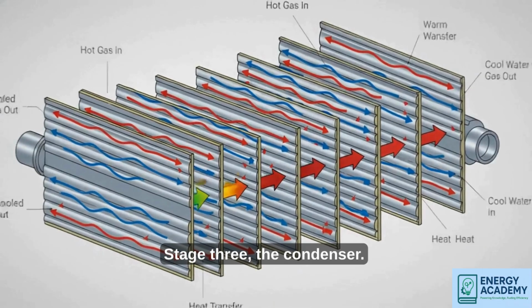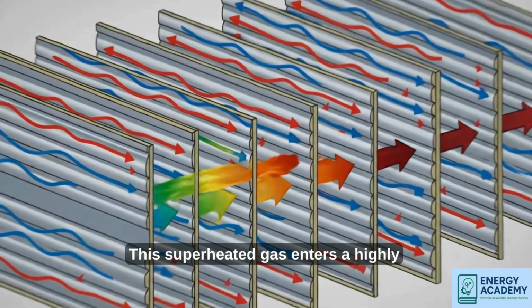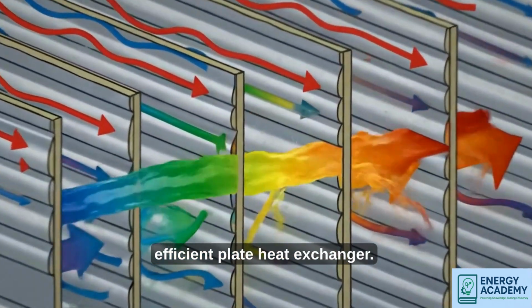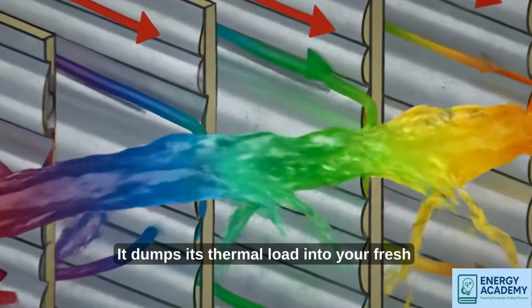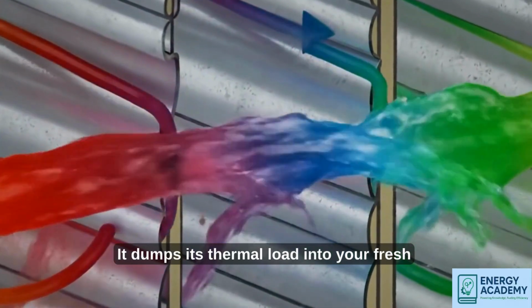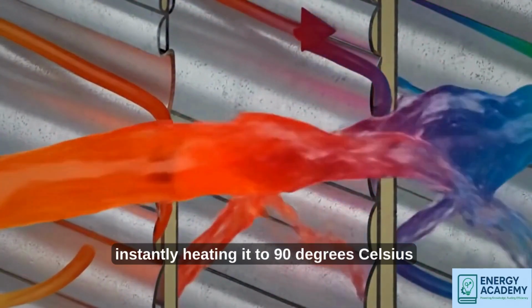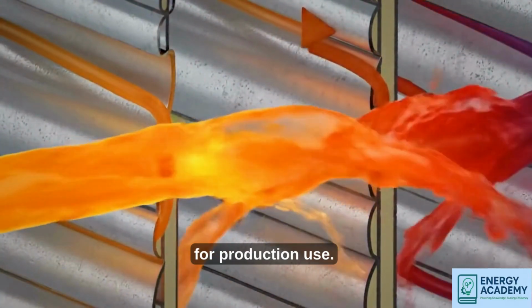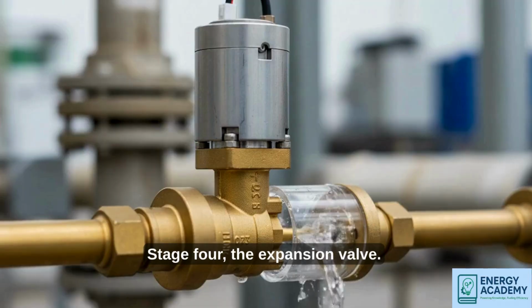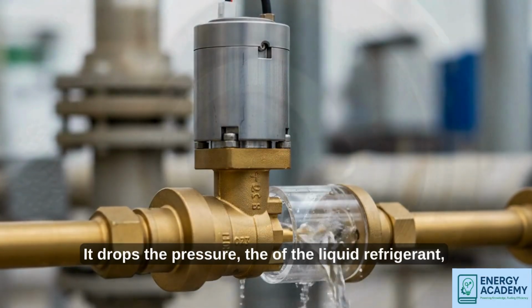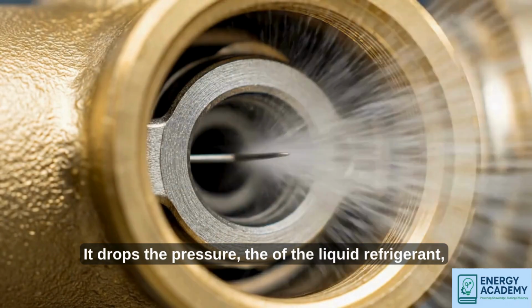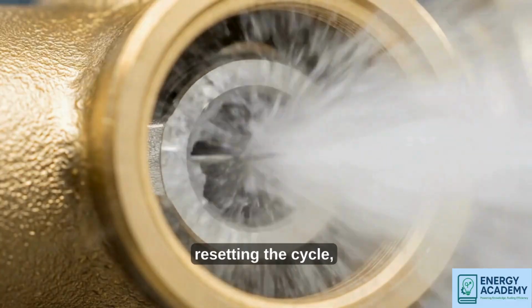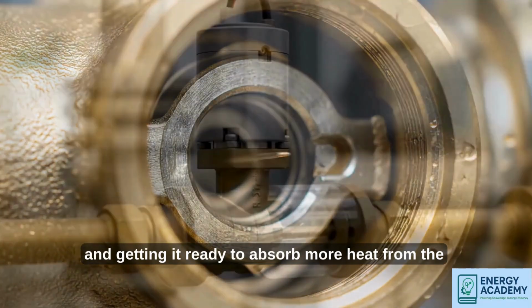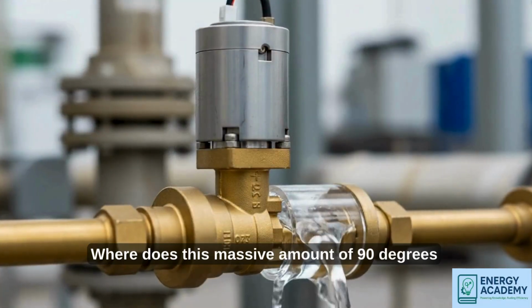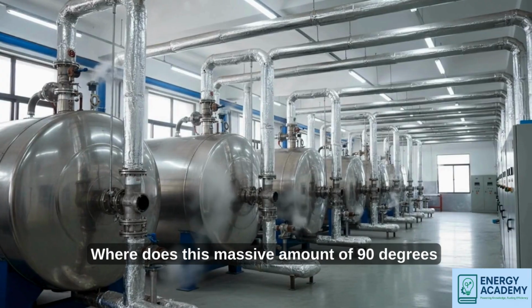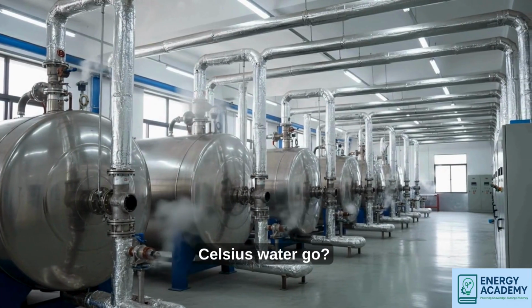Stage 3, the condenser. This superheated gas enters a highly efficient plate heat exchanger. It dumps its thermal load into your fresh process water, instantly heating it to 90 degrees Celsius for production use. Stage 4, the expansion valve. It drops the pressure of the liquid refrigerant, resetting the cycle and getting it ready to absorb more heat from the buffer tank. Where does this massive amount of 90 degrees Celsius water go?